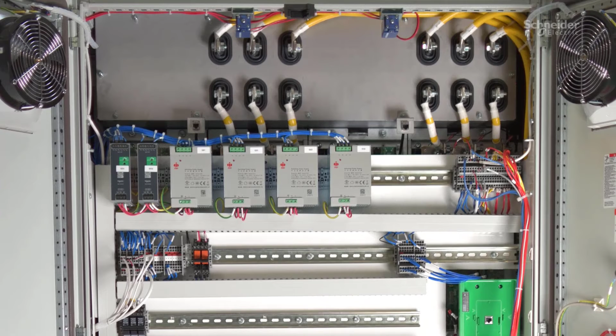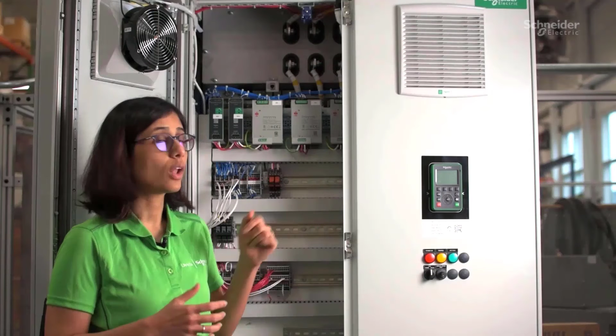Along with these modules, you have DVDT filter on the top. You have your main circuit breaker disconnect which is 100 kA rated. You have your output connection lugs at the bottom. If I close the door, you see the pilot lights and control devices on the door along with the door mounted keypad which helps with easy programming and diagnostics of the drive. These drives come in 4 different sizes, the smallest being 600mm wide.